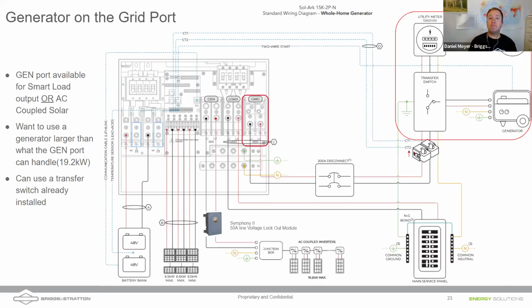Before we move on, Jim Carey comes in with a great question here. He says, as I understand, the solar converter shuts down the load when it's updating software or during maintenance issues. Is there any way to integrate a transfer switch to bypass the inverter and feed the connected loads? So Daniel, I can give you that, or I can just answer it. The answer is absolutely. In fact, Solark recommends that you install a 200 amp bypass transfer switch together with your Solark to avoid these complications.